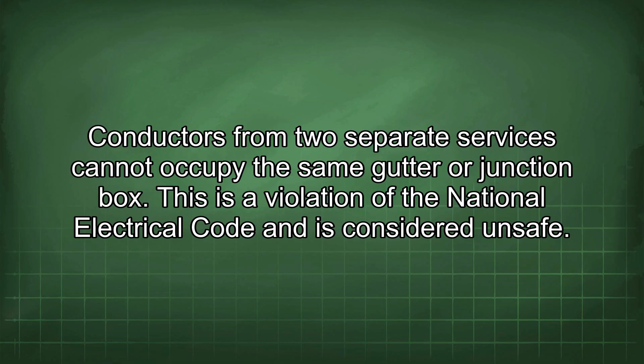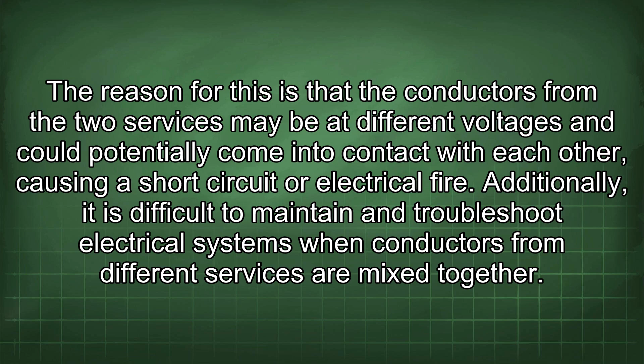Conductors from two separate services cannot occupy the same gutter or junction box. This is a violation of the National Electrical Code and is considered unsafe. The reason is that conductors from the two services may be at different voltages and could potentially come into contact with each other, causing a short circuit or electrical fire.